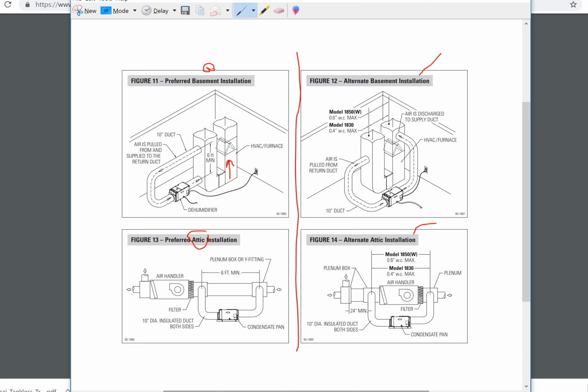The first thing for return to return is that because the fans inside the air handling unit and the dehumidifier could potentially operate in series, they work easier. So there's less load on the air handler blower and there's less load on the dehumidifier blower. And the CFM remains constant. If anything, the pressure between the two fans could enhance each other, not fight each other. So that's a big part of why return to return is preferred, because it's easier on the air handler blower and it's easier on the dehumidifier blower.